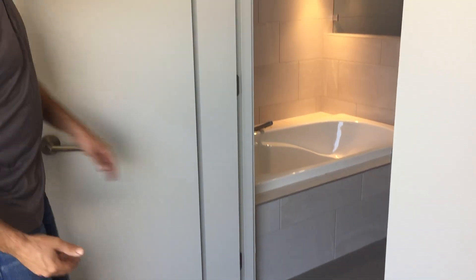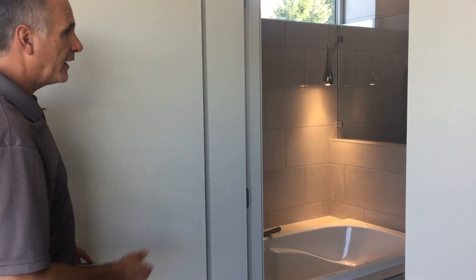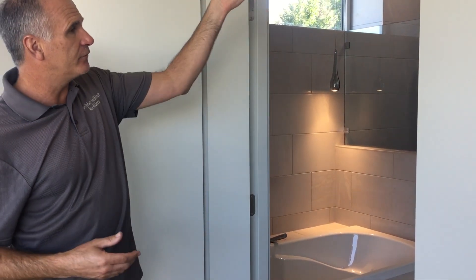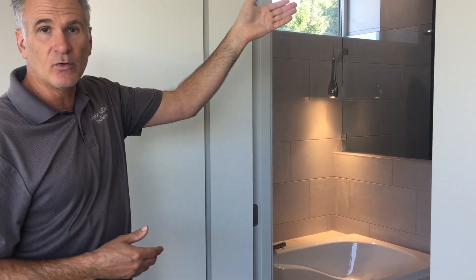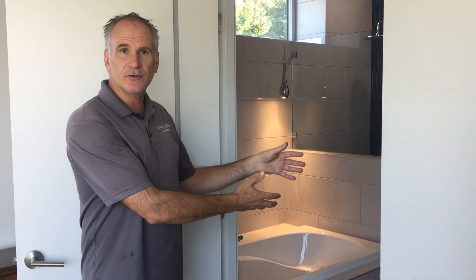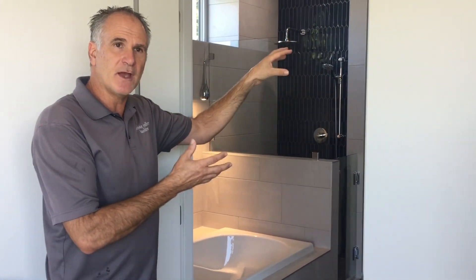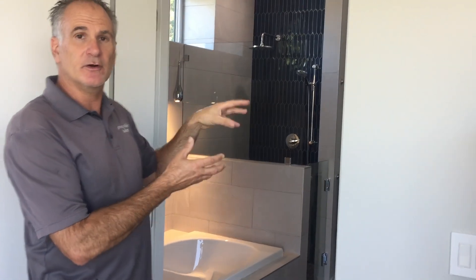You can see that the baffle or vent channel is on the opposite side, so the air actually passes through the core of the door. The bathroom, right above the toilet at the back corner, is where we have the exhaust port. So the fresh air comes into the bedrooms, moves across the room into the bathroom, and gets pulled out — and that's not a bathroom fan, that's an HRV return air duct. The stale air and moisture get pulled back through the HRV core and expelled outside, keeping the airtight house completely balanced.